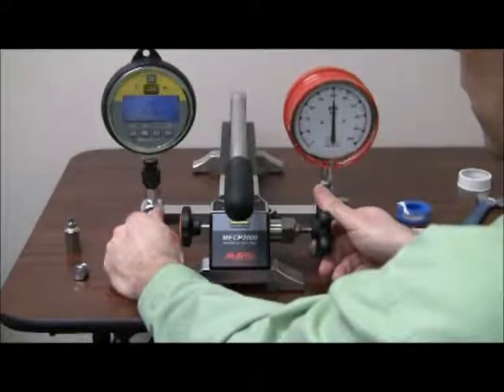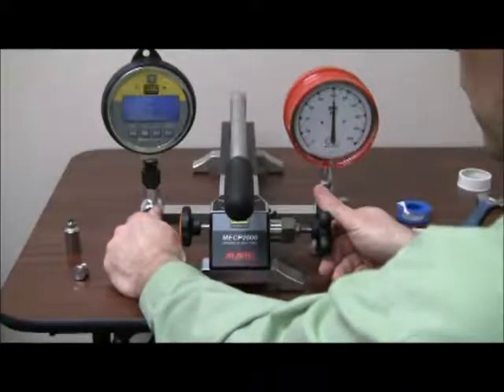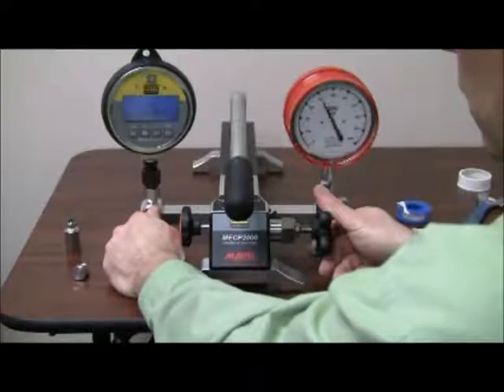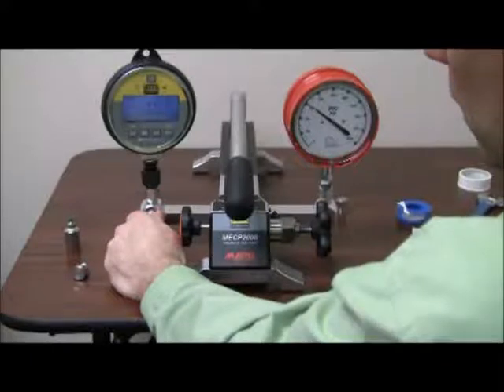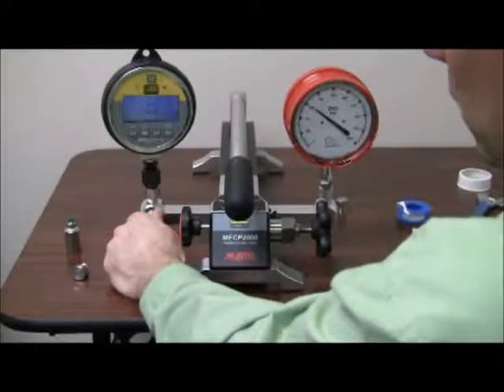We're going to bleed back down. As you see here, we have a steady pressure reading, meaning there's no leaks in the system.